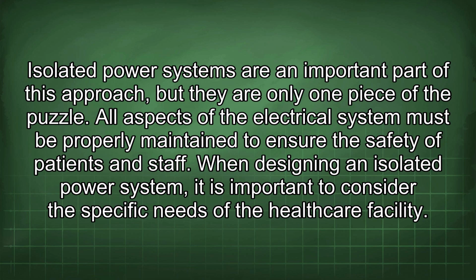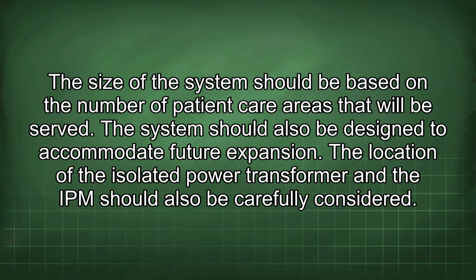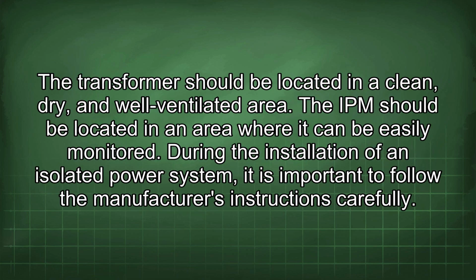When designing an isolated power system, it is important to consider the specific needs of the healthcare facility. The size of the system should be based on the number of patient care areas that will be served. The system should also be designed to accommodate future expansion. The location of the isolated power transformer and the IPM should also be carefully considered. The transformer should be located in a clean, dry, and well-ventilated area. The IPM should be located in an area where it can be easily monitored.